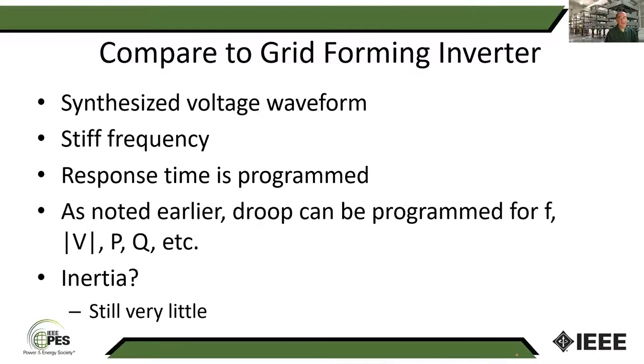For the grid forming inverter, now we have a synthesized voltage waveform. We could have an extremely stiff frequency, so we could control that frequency on the order of milliseconds to tens of milliseconds compared to seconds for a rotating machine. The response time is basically a design thing for the programmer. You can also program various types of droop, whether it's frequency or voltage or even real and reactive power. Most of these have very little inertia because you've got a little bit of energy storage on the DC link, but that's about it. So if you wanted to imitate inertia, what would you do?